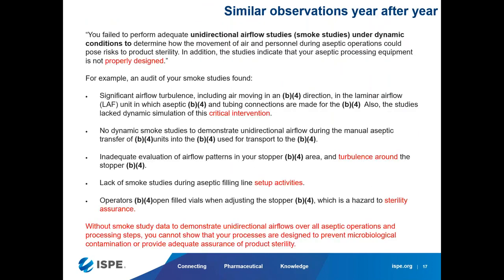Let's start with this. These are similar observations year after year for the past 5 years - why? You failed to perform adequate unidirectional airflow smoke studies under dynamic conditions to determine how the movement of air and personnel during aseptic operations could pose risk to product sterility. In addition, the studies indicate that your aseptic processing equipment is not properly designed. This is going to increase even further.